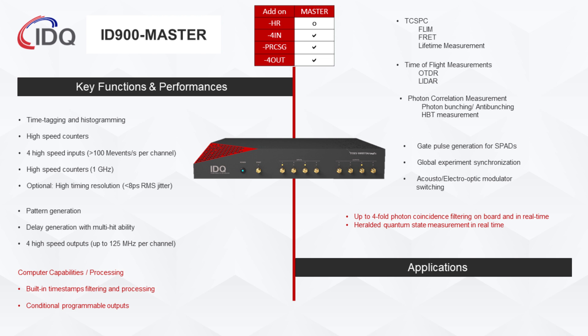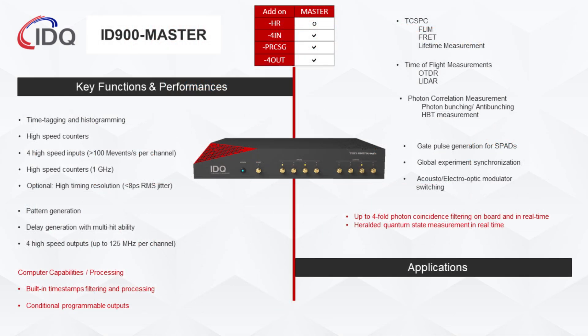The onboard FPGA is the key to avoiding heavy data transfer to your PC. The time controller's computational engine is designed to handle the bulk of the processing load between when a signal is received and when usable data is ultimately transferred to your PC. Conditional filters, start-stop histograms, coincidence extraction, count rate, and other intensive calculations are all handled onboard thanks to the ID900's unique built-in computing power.